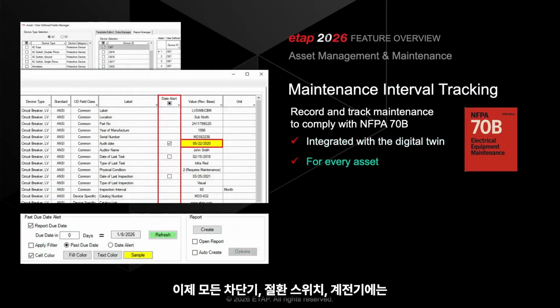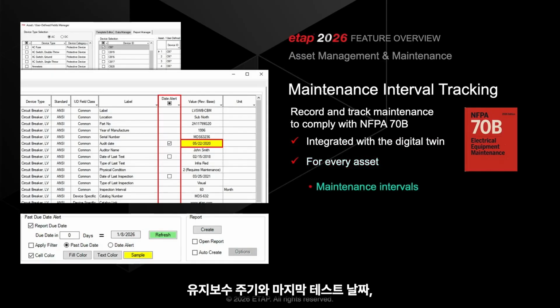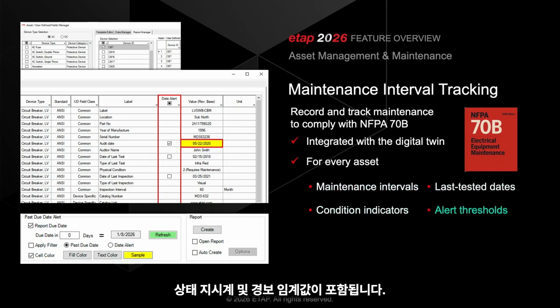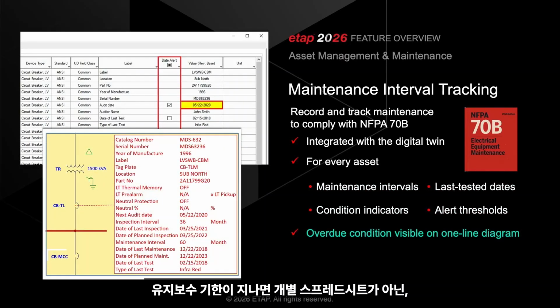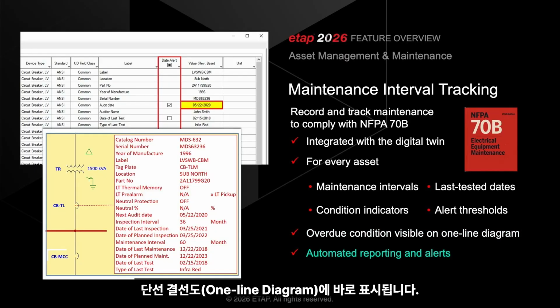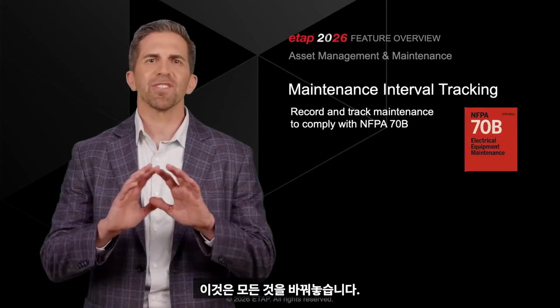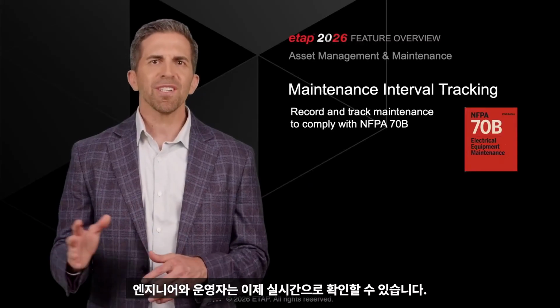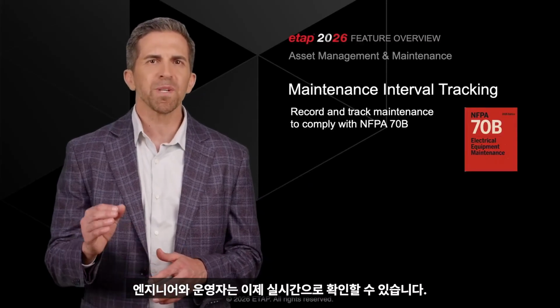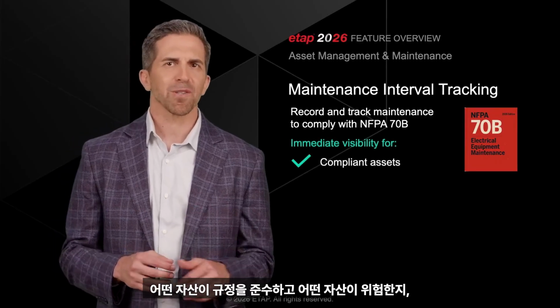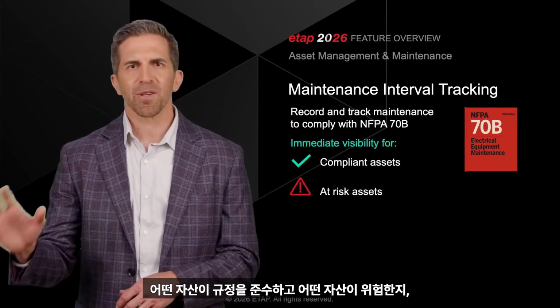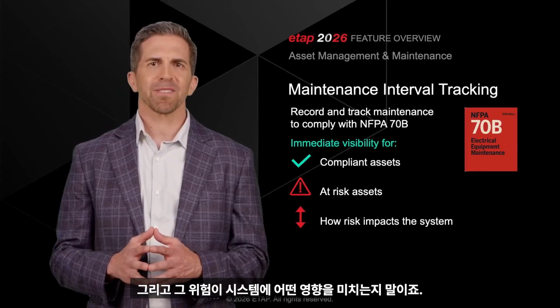Every asset, breaker, transfer switch, and relay now carries maintenance intervals, last tested dates, condition indicators, and alert thresholds. And when maintenance is overdue, this doesn't sit in a separate spreadsheet. It is visible directly on the one-line diagram. This changes everything. Engineers and operators can now see in real time which assets are compliant, which assets are at risk, and how that risk impacts the system.